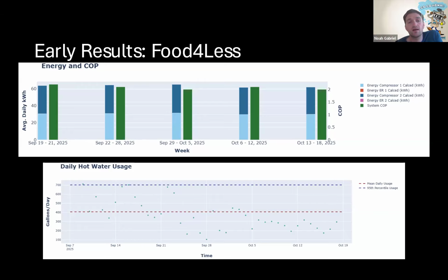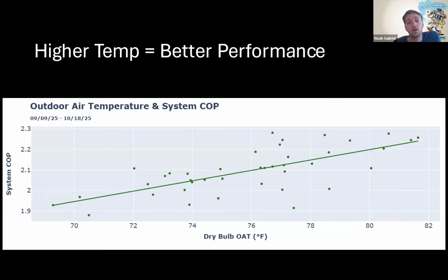And you can see some really high hot water use days, going all the way up to 700 gallons. So that could also be taxing the system. Could also be a recirculation thing where the recirc load is kind of putting some strain on the compressors. For both Krogers though, we did see some pretty clear performance that it's outdoor air temperature, but it's really the air temperature in the rooms here that's going to lead to way better performance. So when you do get all that waste heat and it's about 80 degrees in the room, you're getting closer to like a 2.3 COP. So that's pretty darn good.